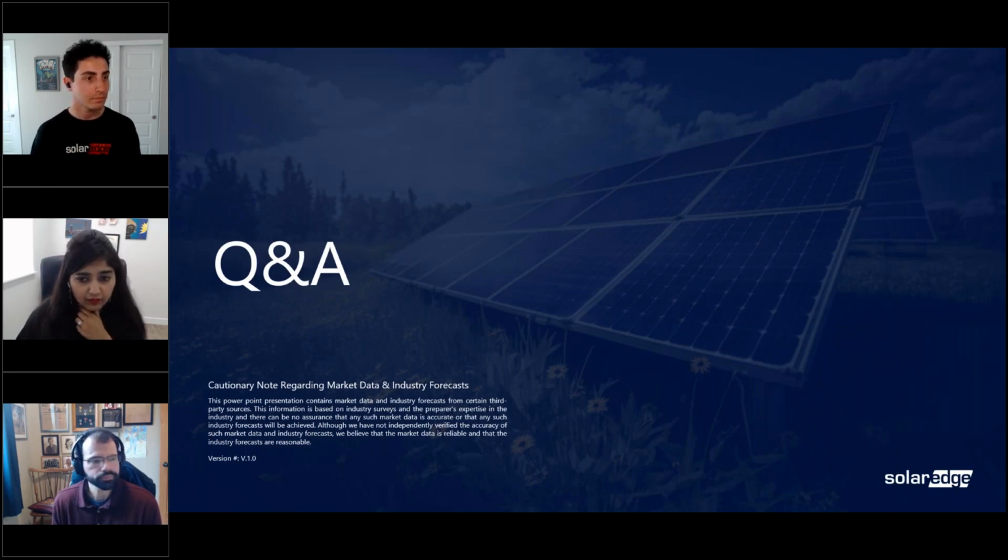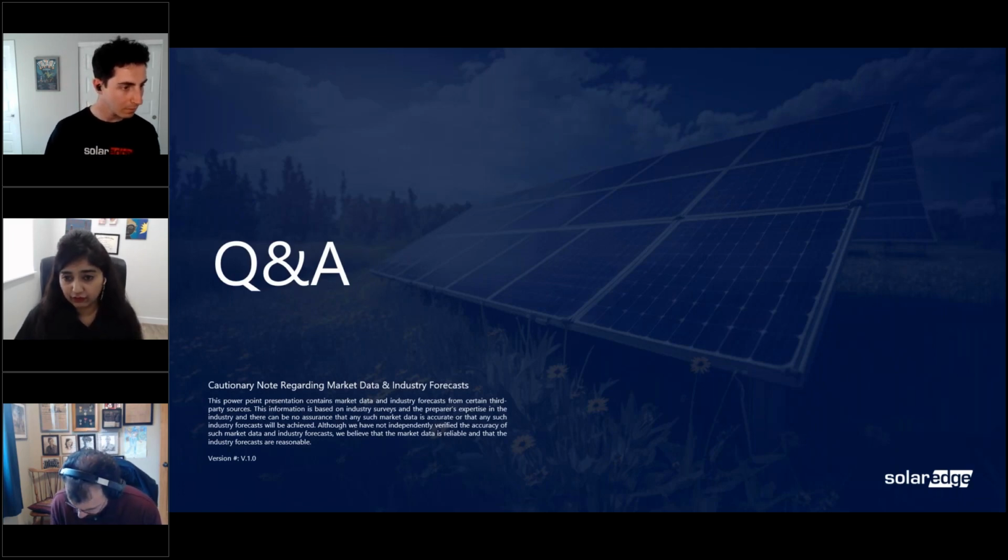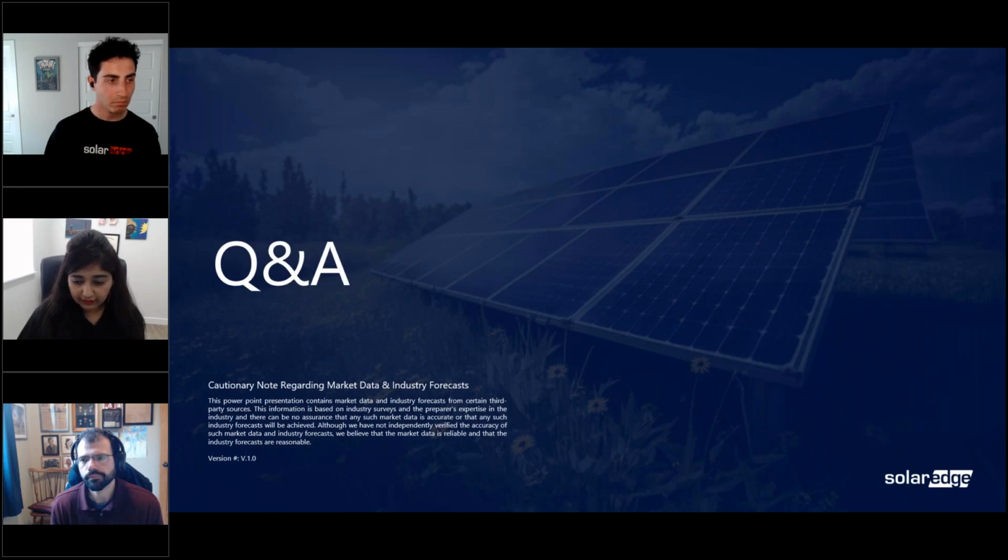Thanks, Jacob. We'll take maybe one more question here. So firefighters are used to expecting 80 volts within the array, and now with 1000 volts allowed, how would they know the difference, and are there any signs? This is an interesting one because during a fire situation, it's almost impossible to tell the difference. So you wouldn't know what the voltage in the array is after rapid shutdown is activated, and there are no additional signs within the array level. So this is definitely a gap in the code that needs to be addressed. So I'll leave it at that.